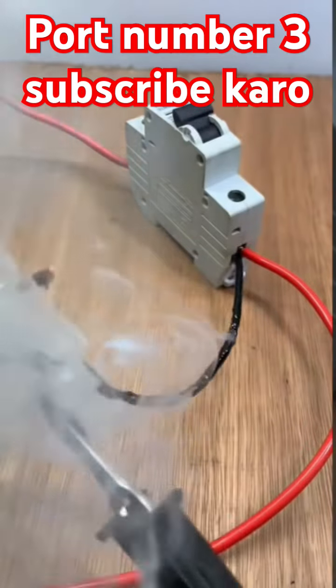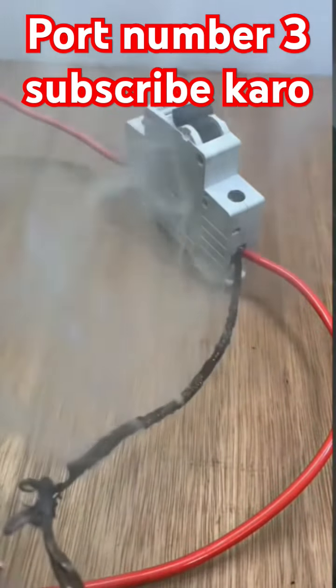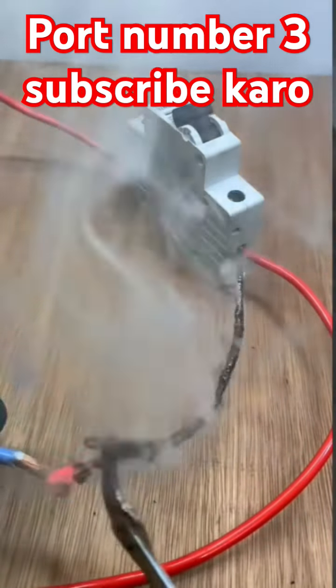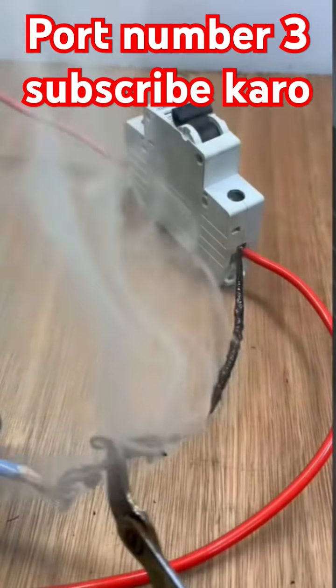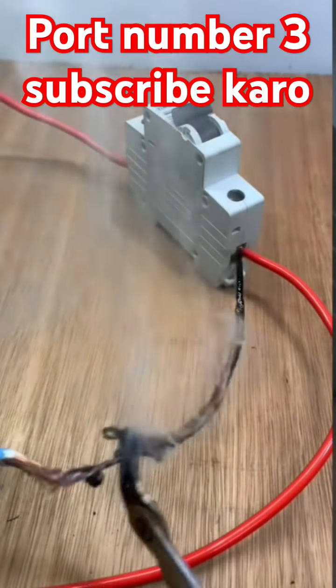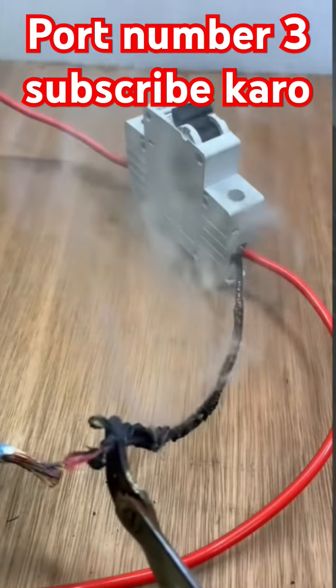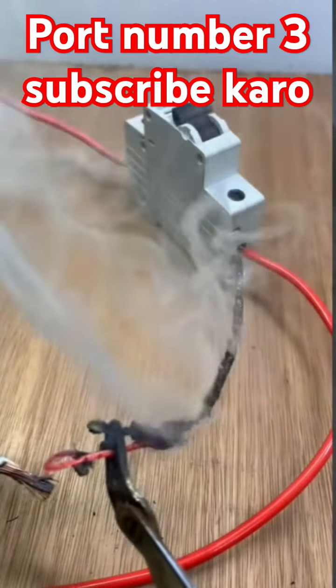Here, look, I'm causing an overload. Look what the 1.5mm wire is doing. The circuit breaker isn't turning it off. It doesn't even seem like this current is going through it. It could be passing half the current. I'm passing about 40 amps here.